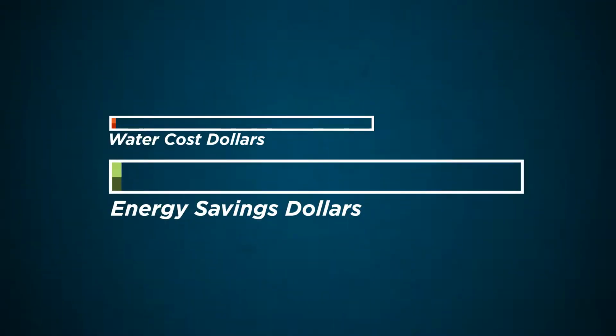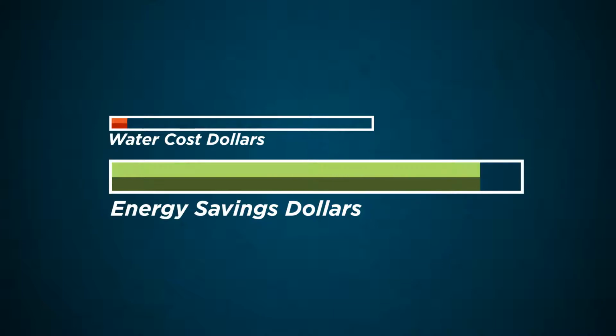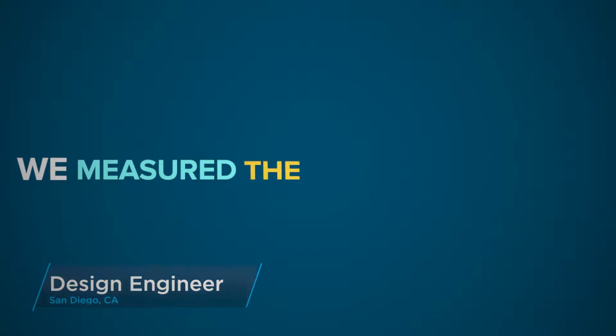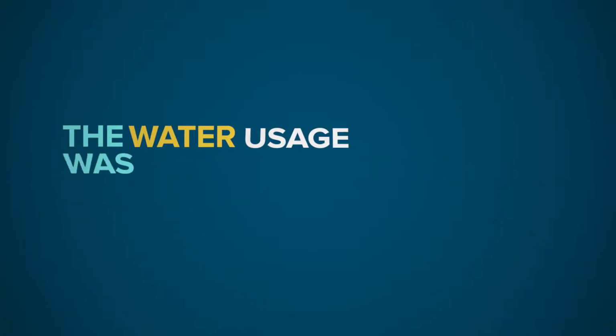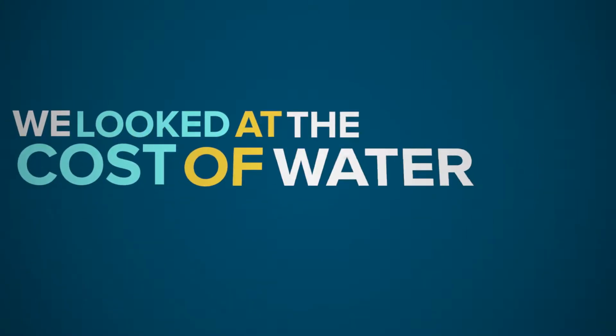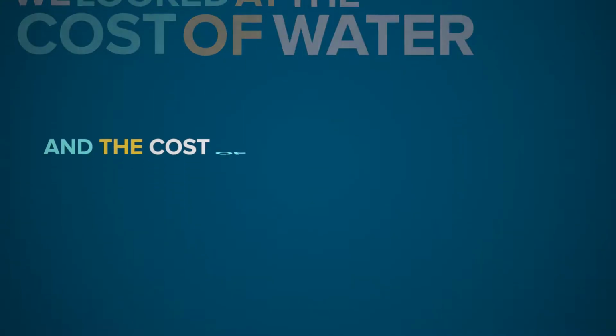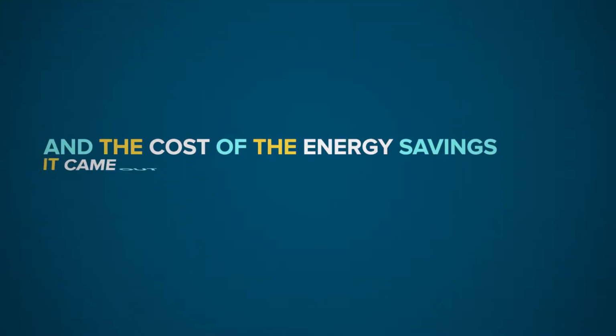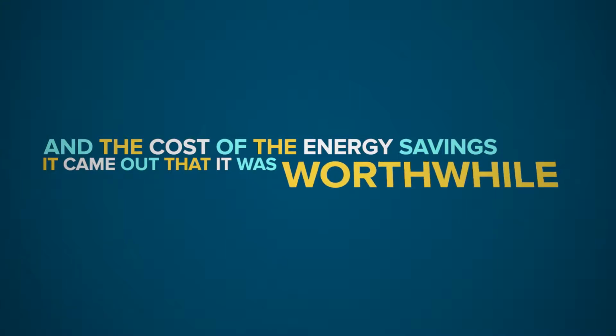Evaporative cooling technologies of today are designed to minimize water use and deal with a range of water supplies with varying quality. The money saved from reduced electricity consumption and peak demand can be used to offset the cost of the water used, which is typically only 3 to 15% of the electricity savings. And we also measured the water usage. The water usage was reasonable. And we looked at the cost of water and the cost of the energy savings, and it came out that it was worthwhile.